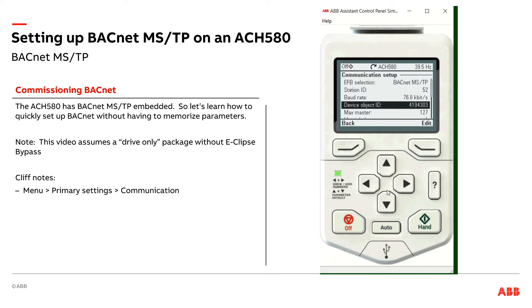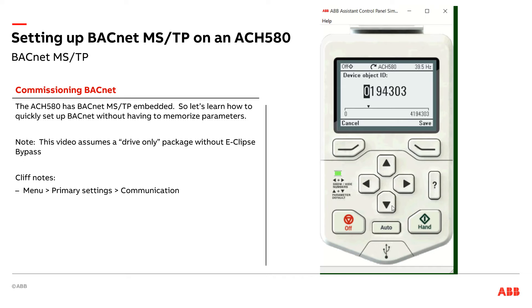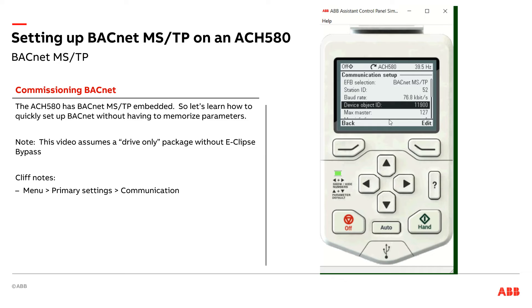Then I have my device object instance ID. This is the number that needs to be unique within the entire network. So let's say mine happens to be — let's say 11,900. There's my device object instance ID.